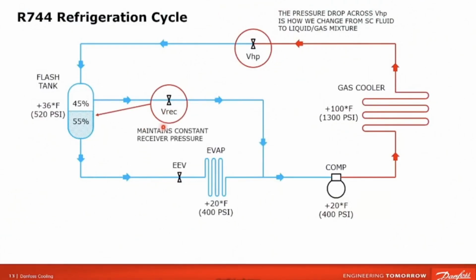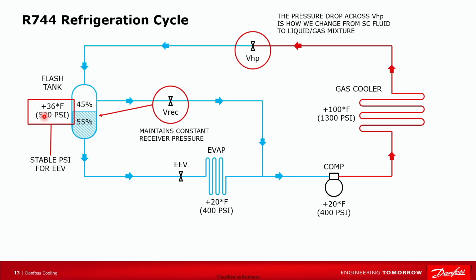The receiver bypass valve serves two purposes. One, it maintains a constant pressure in the receiver. Here we're showing a 520-pound set point. We want to keep that set point a fair amount above the evaporator pressure so we can still push liquid and help the system to circulate. But that also gives us a very stable pressure to feed the expansion valves.